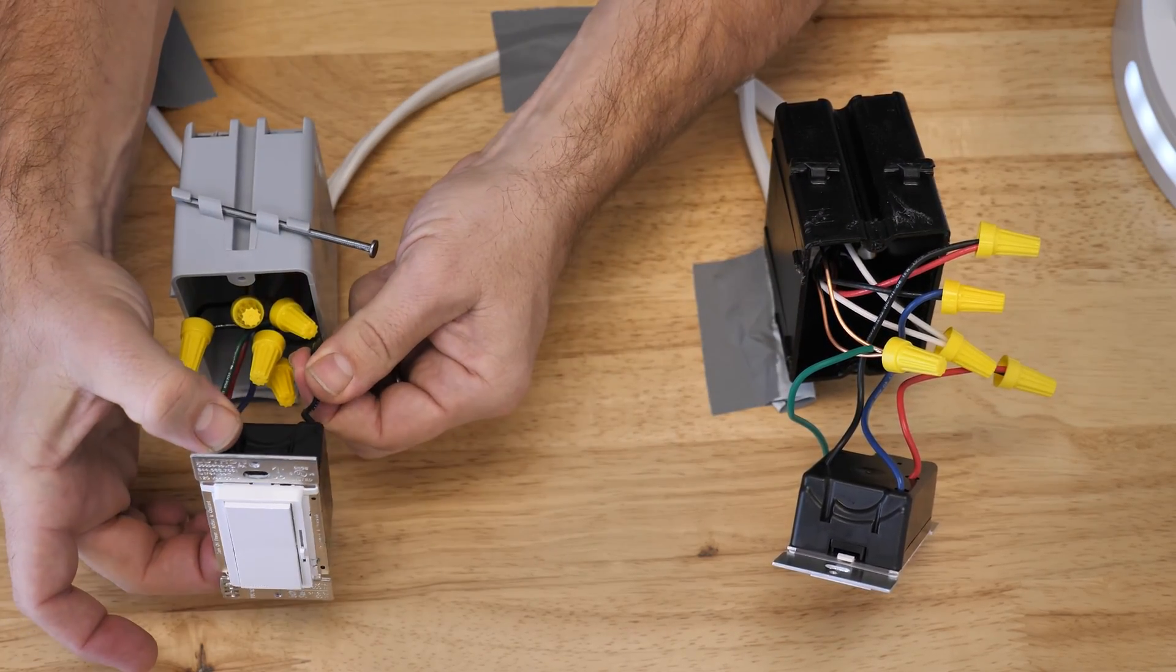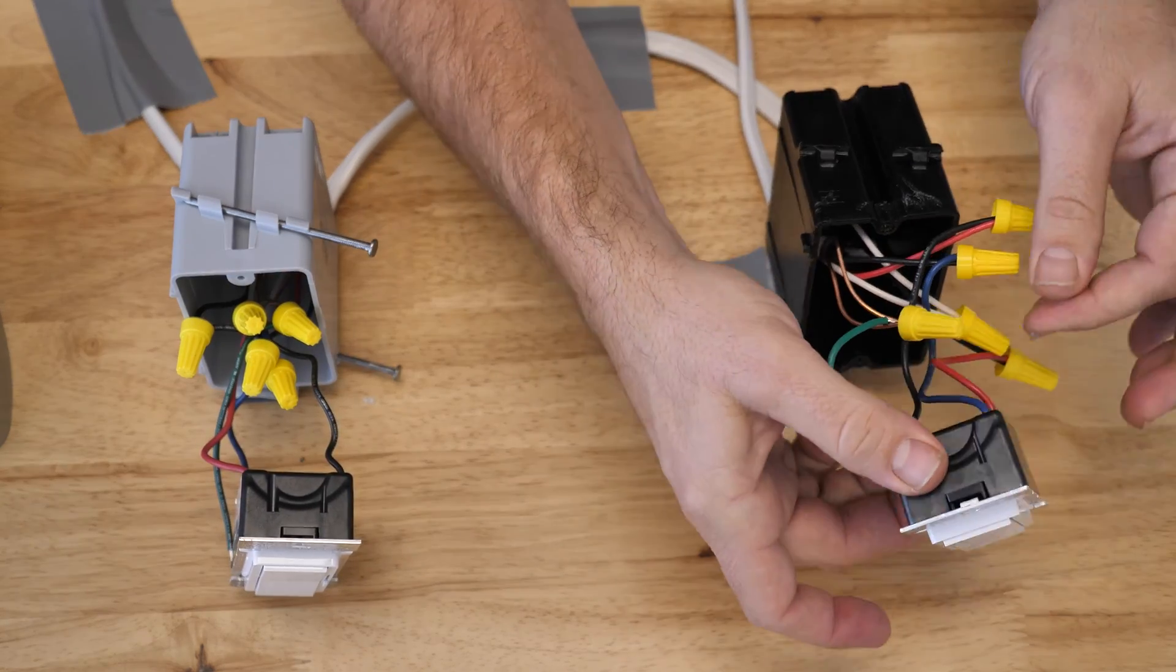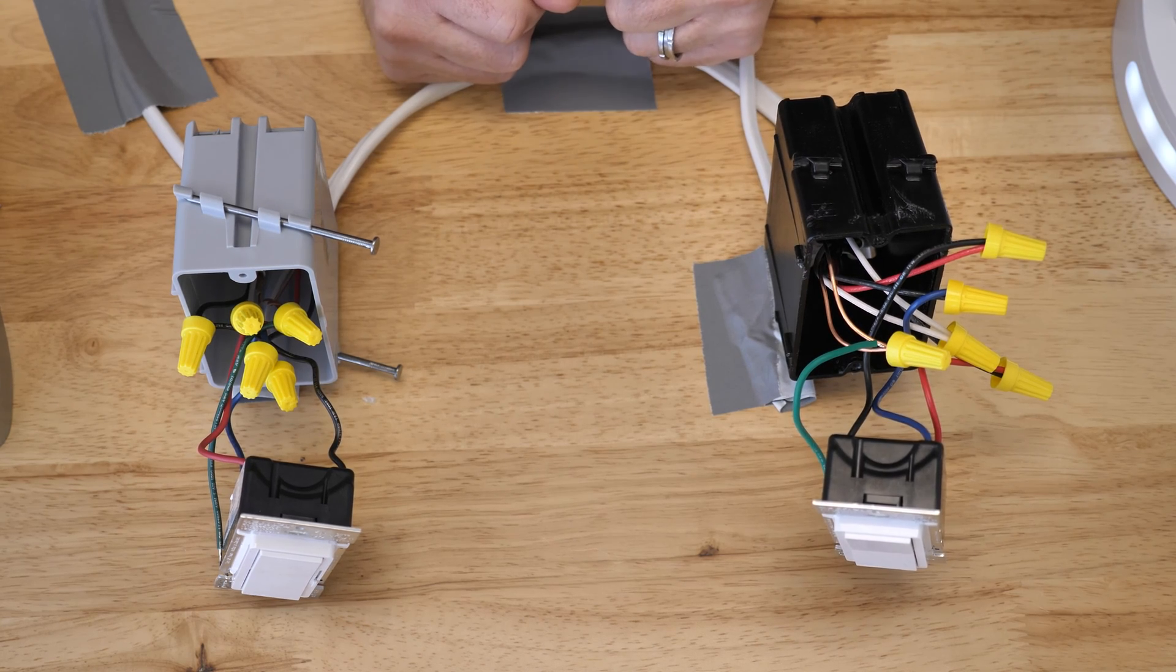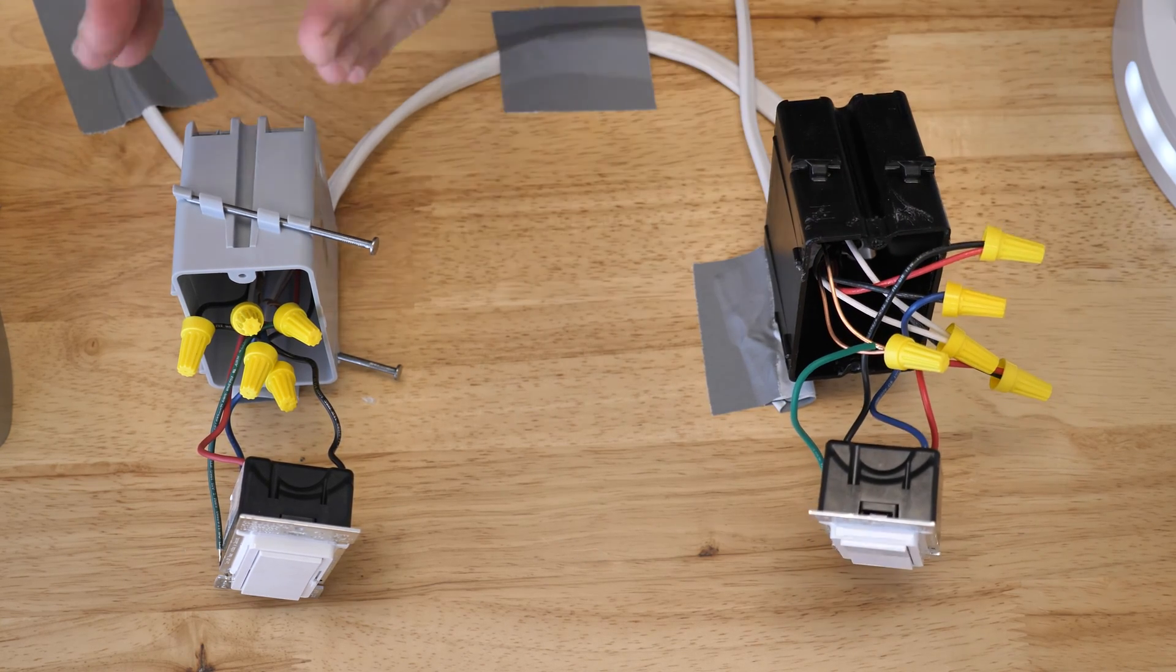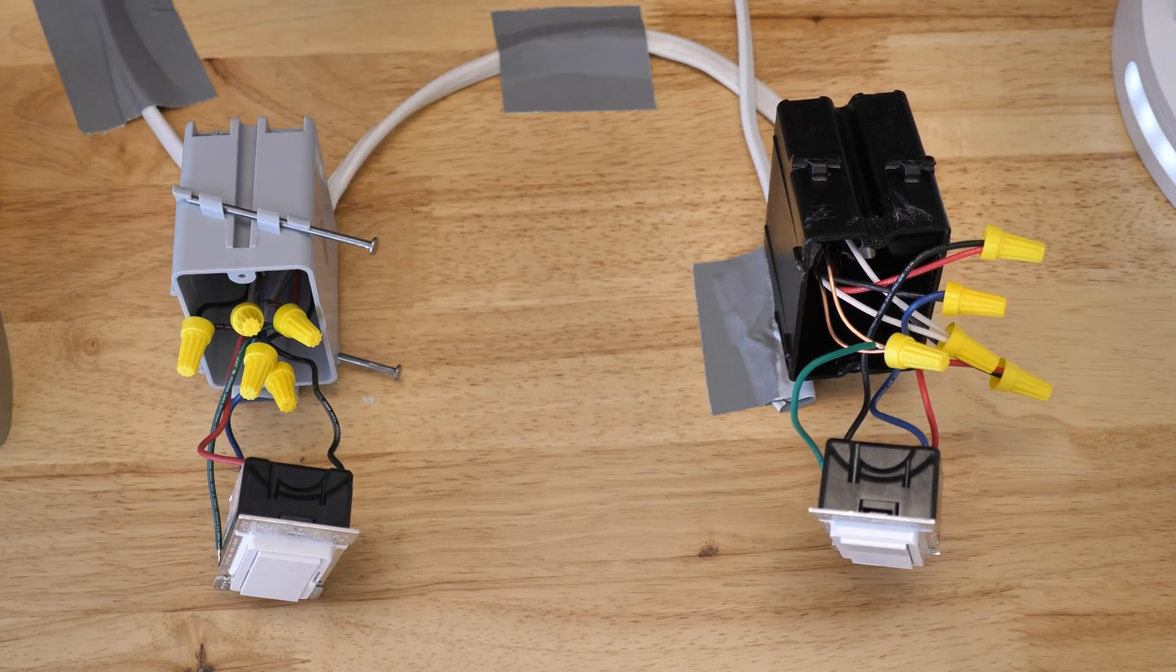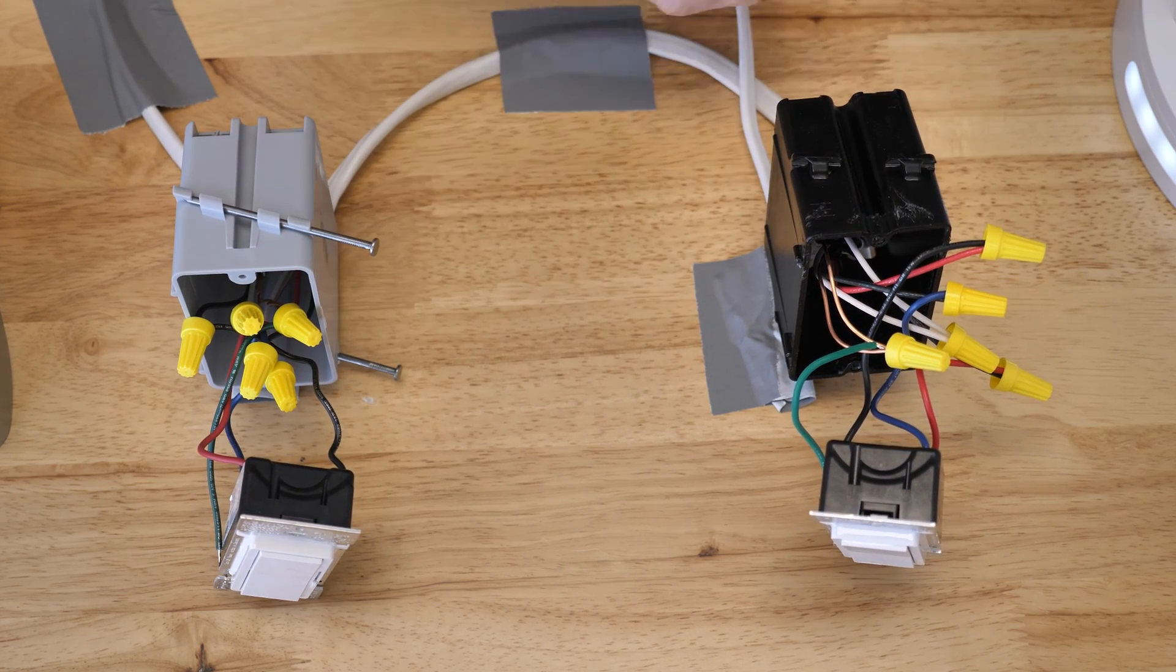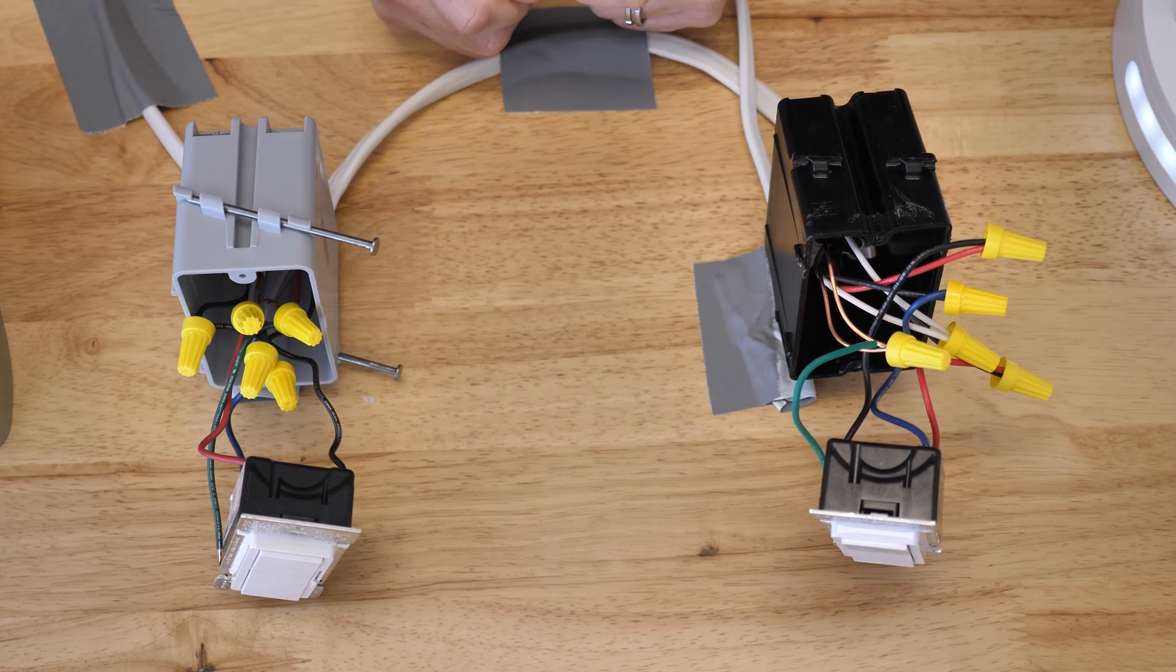Just remember, it's always going to be power in on the main control, and then switch leg out to your light on the other control. The great feature about Lutron is you can actually bring the power in either side, the switch leg out either side. That will work just fine. It does not matter which direction these units are installed in.